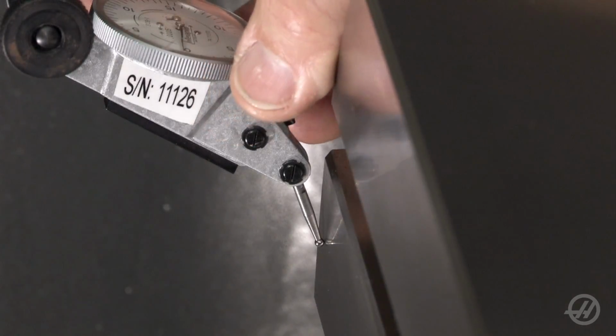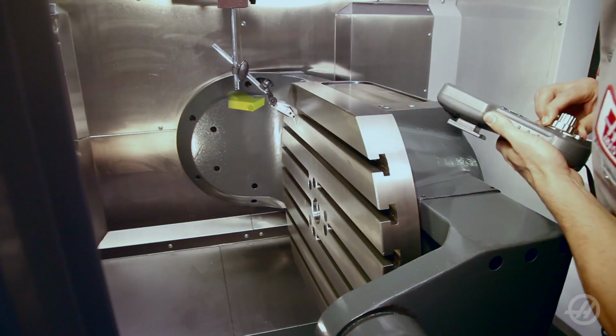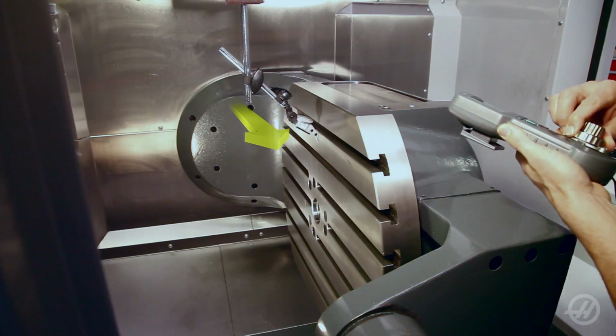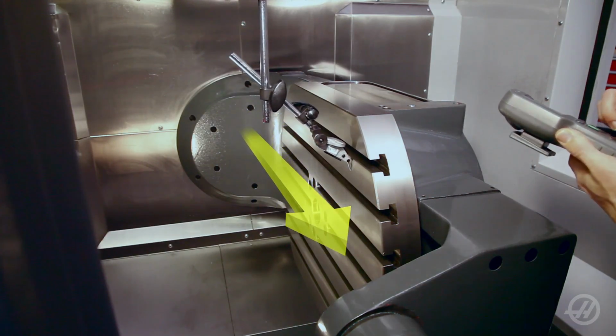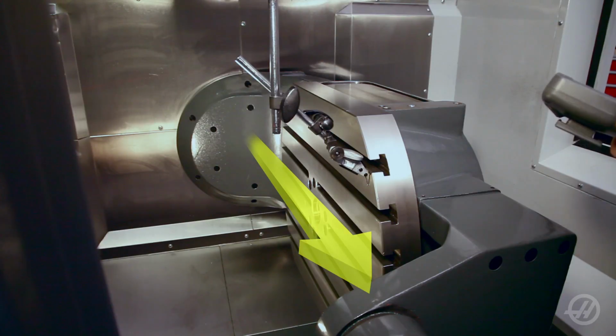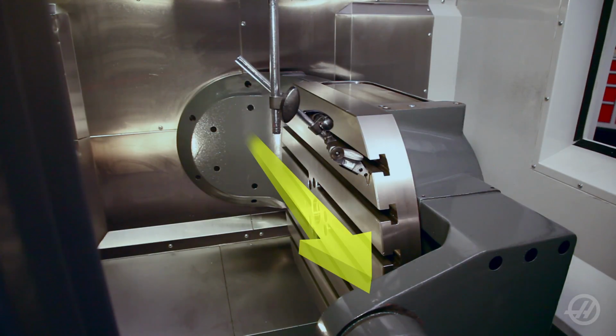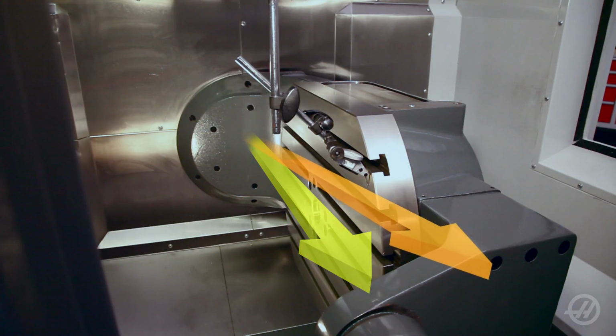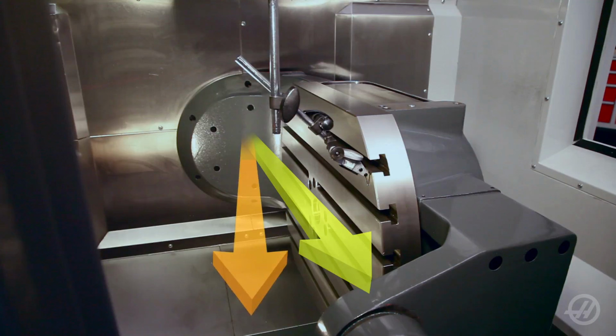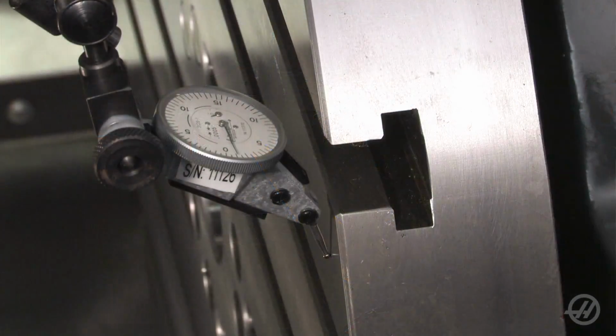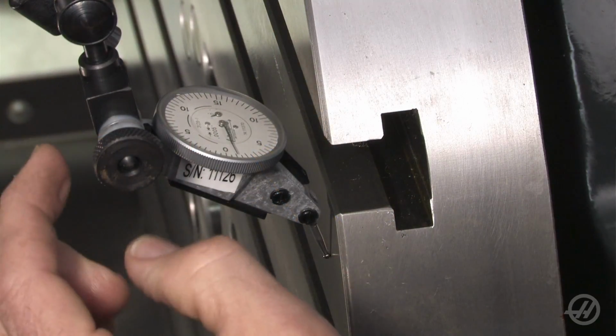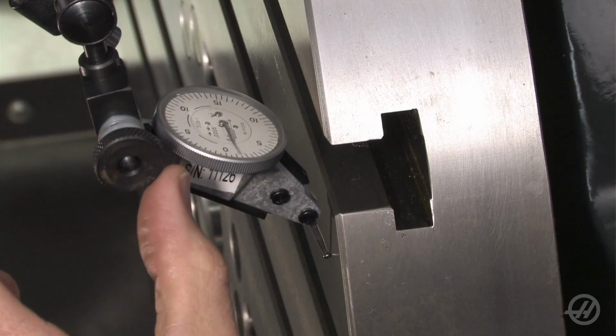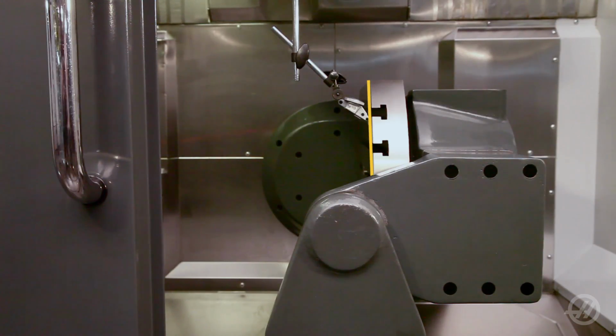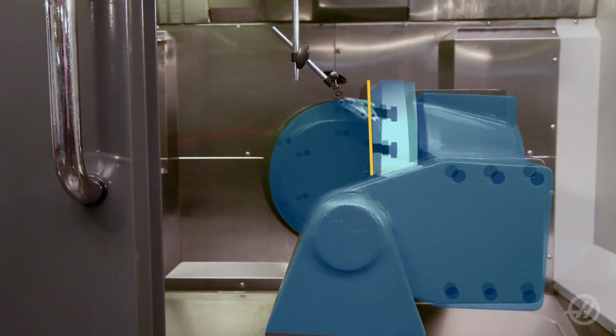Zero the indicator on the table face and sweep forward, jogging Y-axis from back to front over 20 inches. Record the indicator reading, noting both magnitude and direction. This measurement will show us the position of the table relative to the Y-axis in the side-to-side direction. In this case, the indicator shows the table face is angled 1/1000th to the right, away from the Y-axis, meaning the trunnion support is also leaning to the right.